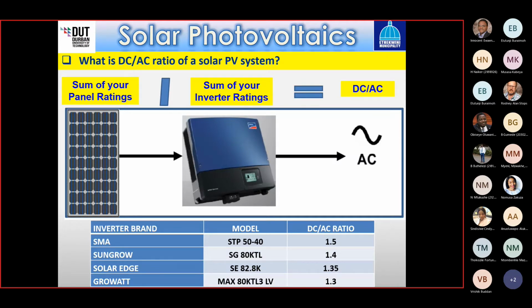So if we look at different manufacturers or brands of inverters, let's look at the SMA inverter. It has a DC to AC ratio of 1.5. What does this mean? It typically means that you could install 1.5 megawatts of solar panels, or DC panels, for your system, and have 1 megawatt of inverters. That's your AC rating. And your system will work fine, so you do not overload your inverter or do anything else to it. And obviously, you've got to look at which brand of inverter you're using and what is the allowed DC to AC ratio. You can't exceed this or you would damage the inverter.